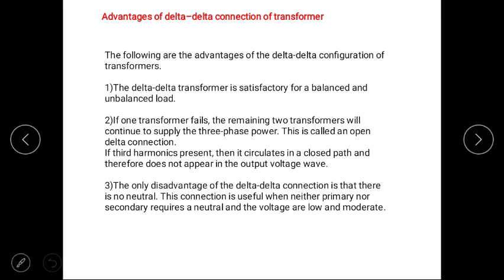Advantages of delta-delta connection: If one transformer fails, the remaining two transformers will continue to supply. It means if in the bank of three transformers, one transformer is damaged or removed for maintenance, the remaining two transformers continue to work but at reduced capacity. If third harmonic is present, it circulates in the closed path and therefore does not appear in the output voltage waveform. The only disadvantage is that it has no neutral — this connection is useful when neither primary nor secondary requires a neutral and voltages are low and moderate.